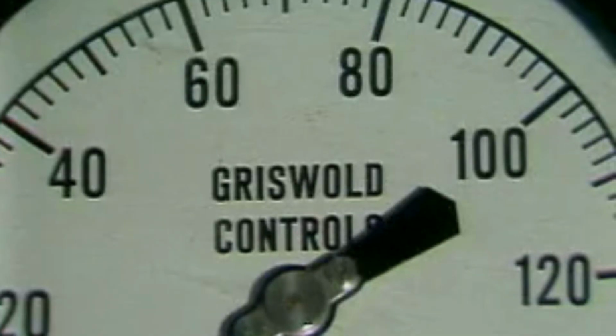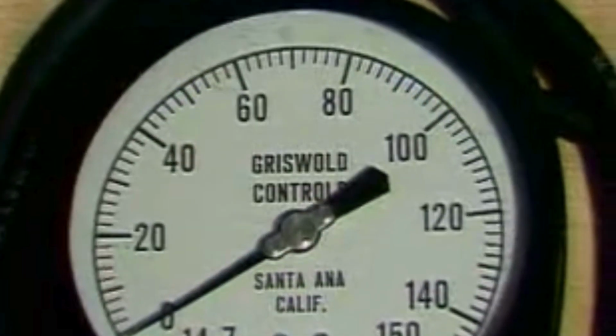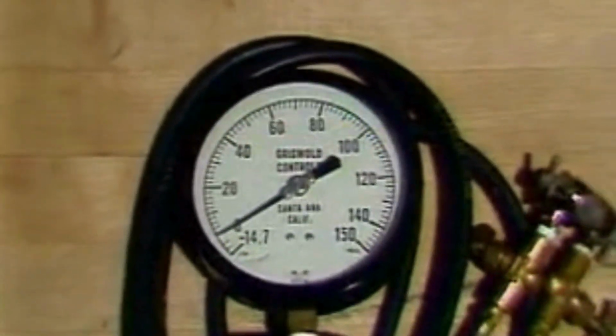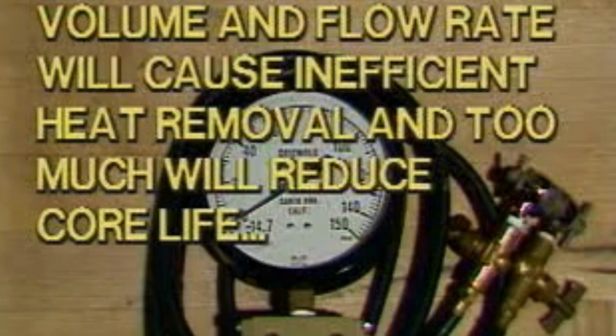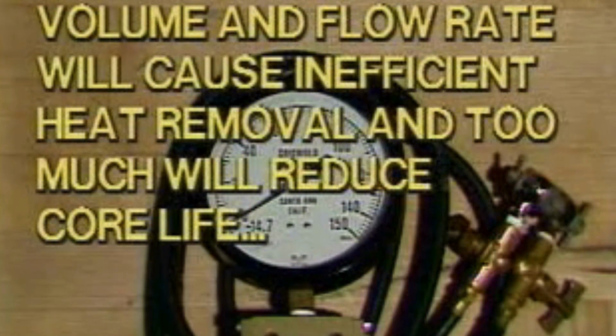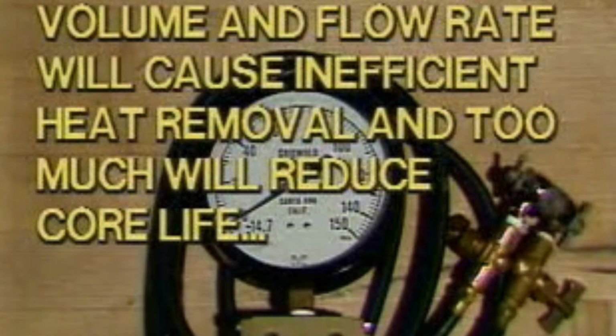Usually, what is done is to place an adjustable globe valve in the supply and/or discharge line to help reduce the volume of supply fluids to the system. The problem with using a valve is to properly regulate pressures and flow rate. Unless you've got a flow meter and pressure gauge, you'll have a hard time balancing the volume and adjusting the flow rate to exactly what it should be. And remember, too little volume and flow rate will cause inefficient heat removal, and too much will reduce core life. Even if you were to get it balanced perfectly, an accumulation of debris in the strainer or a pressure fluctuation would change your volume, so you can see the problem we have.